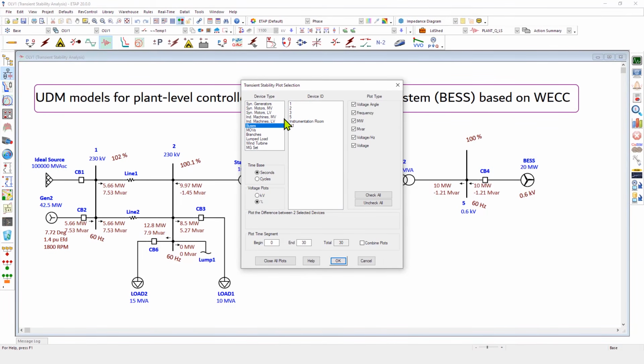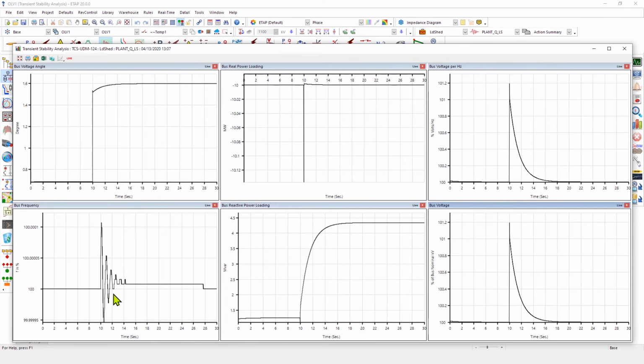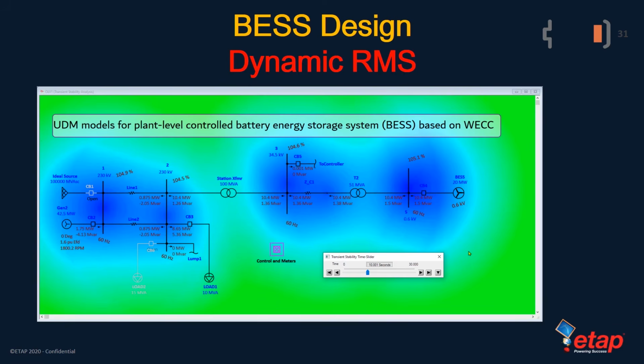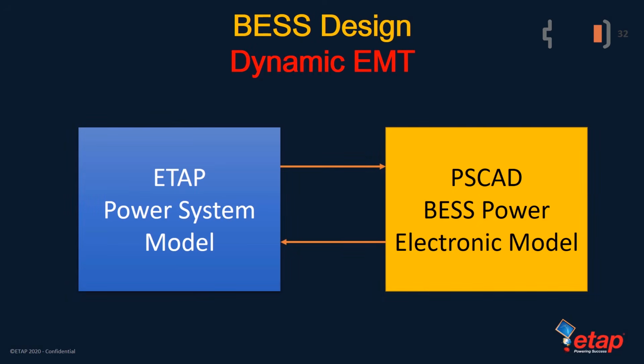You can also observe other things in the circuit, like the bus voltage and frequency and so on and so forth. And once again, observe the disturbances or transients at any point in the system. Now that we have included a UDM model for battery energy storage based on WECC, we can observe what happens when we apply an event and see the effect or the disturbance on our network. This is an RMS simulation, so therefore we can now turn our attention over to dynamic or EMT simulation.